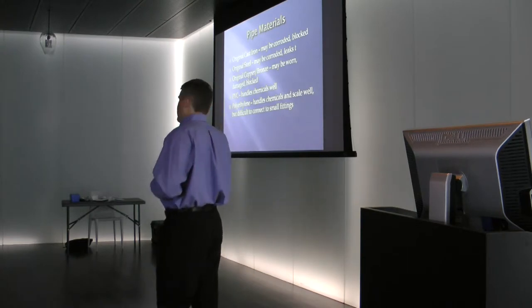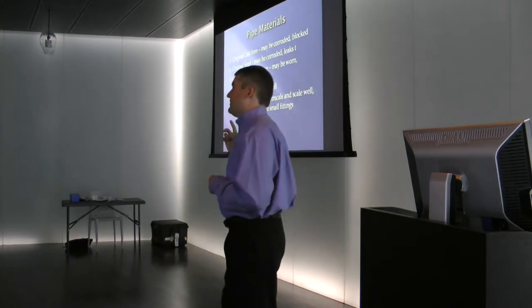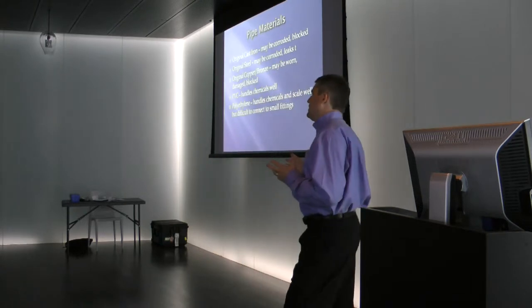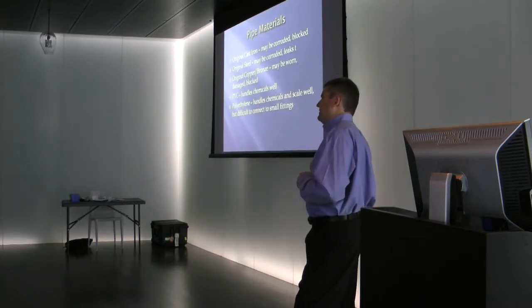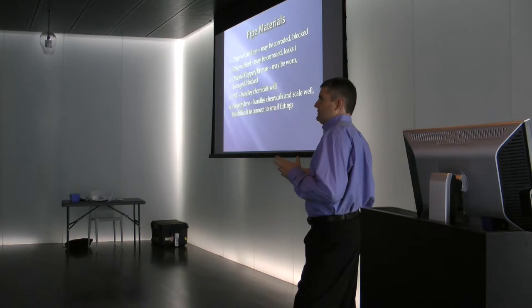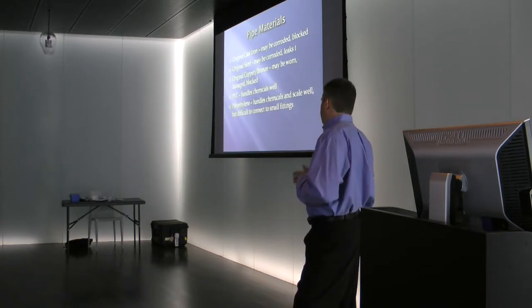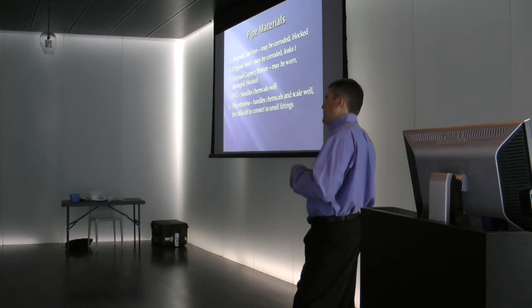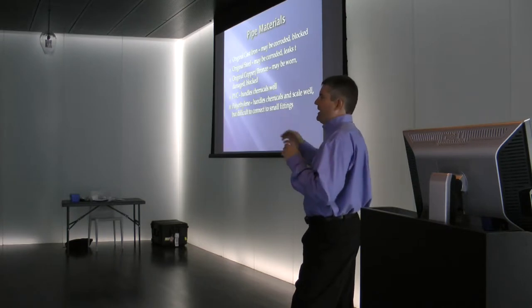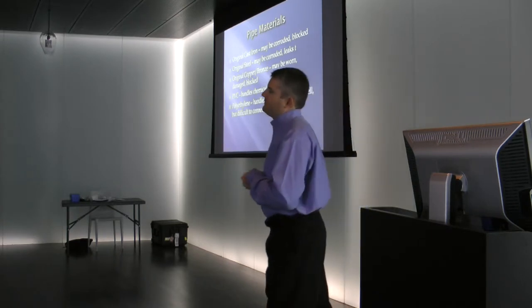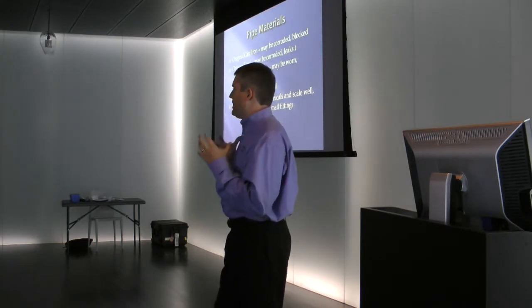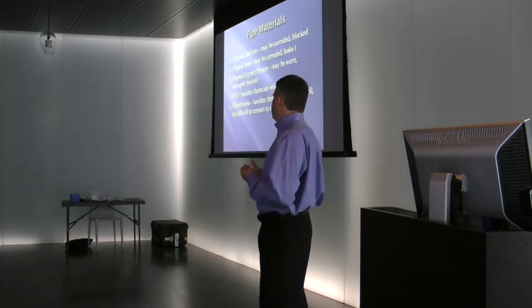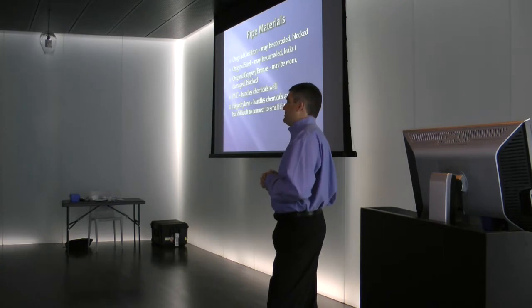One thing I like about polyethylene is that nothing likes to stick to it. It's almost like Teflon, and we've had projects with mineral spring water that would just calcify up and block any pipe, but with the polyethylene, you could just shut off the water for a day and let everything dry out, and everything just falls off the pipe, and you turn on the water and it flushes it out and everything's clean again. So for those occasional projects where you've got really hard water, polyethylene is actually better than even the PVC.